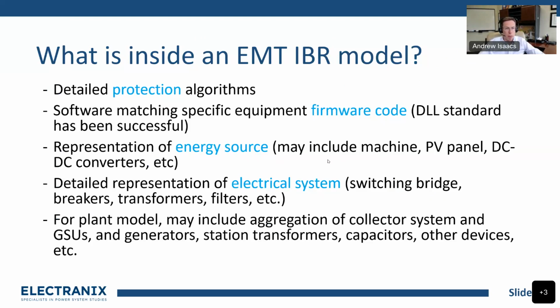So inside an EMT model, we have detailed protection algorithms - that's everything from individual phase quantities. We can protect based on individual phase quantities. We can implement sophisticated protection and measurement algorithms that are actually in the equipment, that can cause the plant to trip. Modern models have software inside that match the specific firmware code that's in the equipment. There's a DLL standard you may have heard of, a joint CIGRE and IEEE standard, under development I suppose, that's been quite successful, and many OEMs have implemented this and built their models this way.